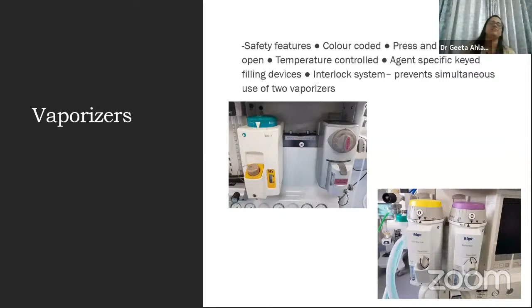The color of the gases should be ensured. If somebody uses it on a Friday and you are using it on a Monday, you should ensure how long the agents have been inside this vaporizer. Some machines have pressure relief valves near the common gas outlet, as I told you. The whole aim is that these valves open to the atmosphere, so that the pressure is in no way transferred to the patient, and it is relieved before the common gas outlet.